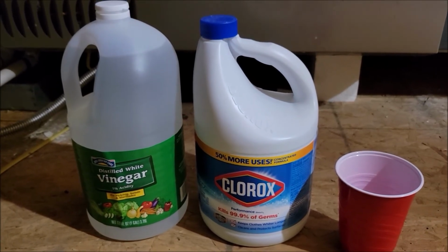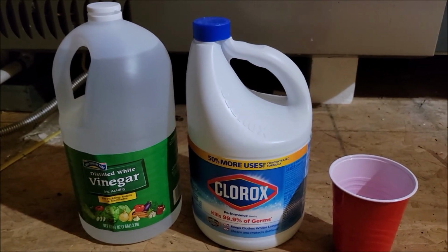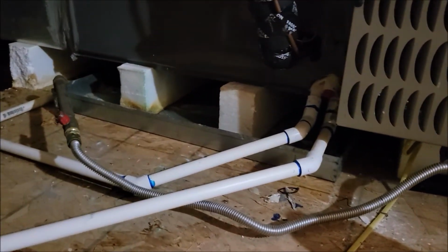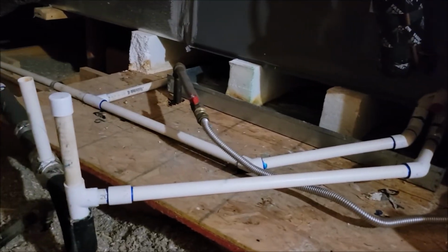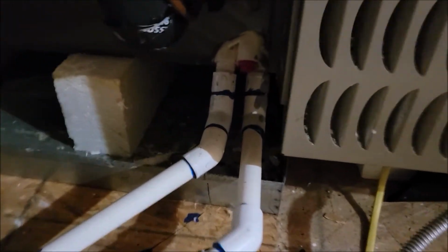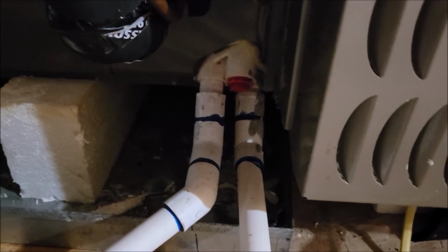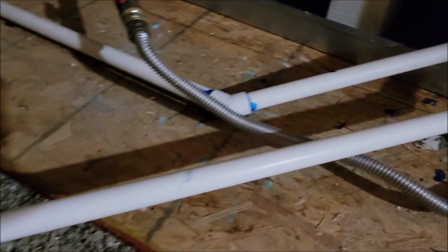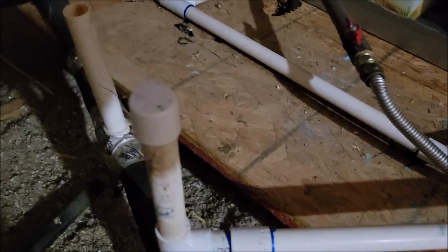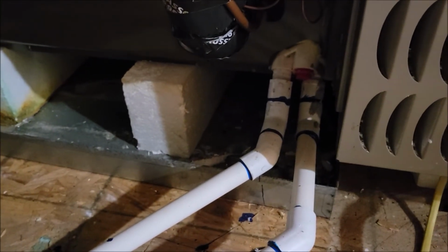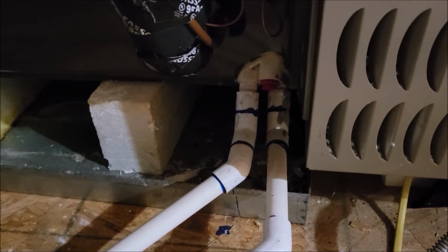Does that mean you can't? No. I mean, you do what you want, right? And especially on a unit like mine, look at how long those drain lines are and how far they are away from the unit. Both of my lines drop pretty significantly right out of the unit. So the chances that me slowly pouring bleach in these clean outs here and that chlorine getting back into the unit is pretty slim. But not everybody's unit is like this.